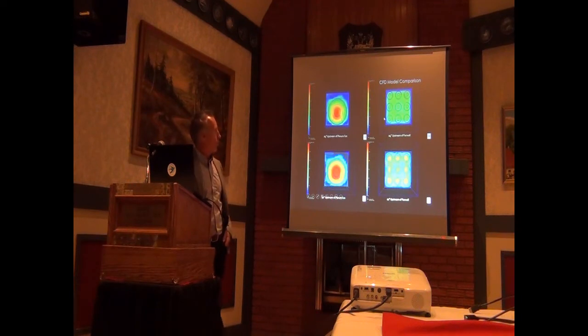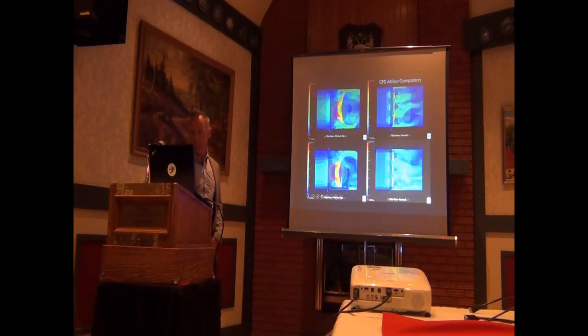If you go over and compare the fan wall, you can see this with the multiple fan wall fans in there, you've got a very uniform wall of air moving through the system, how the system was designed. Everything else in the system, so why not have the fans do that? You can see that again, 12 inches upstream.